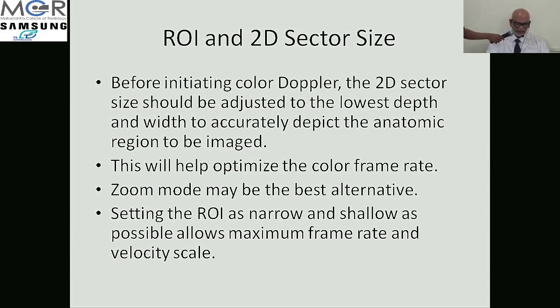ROI means region of interest, and 2D sector size. Before initiating color Doppler, the 2D sector size should be adjusted to the lowest depth and width that accurately depict the anatomic region to be imaged. Try to keep the width of the color Doppler sector to a minimum and the depth to a minimum, so that it can give you the best possible result. This will help optimize the color frame rate. Again, frame rate is important in 2D everywhere. So zoom mode may be the best alternative.